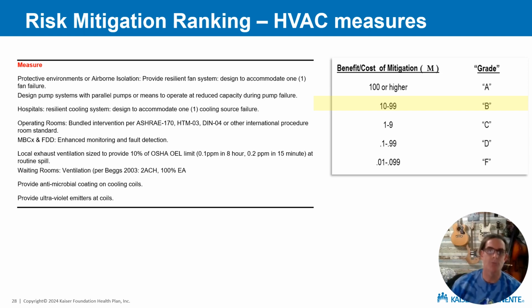For airborne isolation rooms, pumping systems, cooling systems, it makes sense to have 2 fans or pumps rather than just 1. We're not talking about N+1. This is not redundancy. There's no extra components talked about on this slide. This is reduced capacity during a failure event.